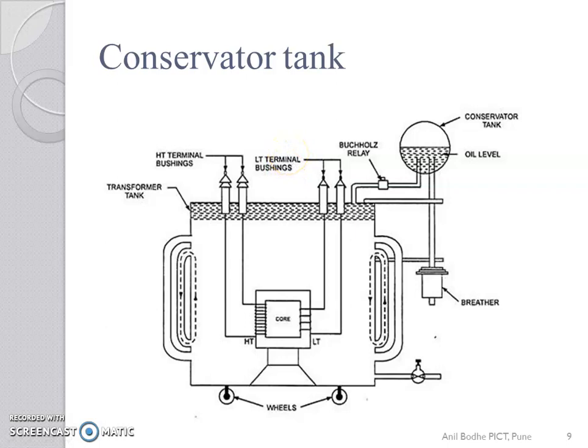Let's elaborate on it. Transformer secondary current depends on load. Transformer secondary current depends on load, and the transformer load is never constant. Because of this varying load, the transformer secondary current is also changed, and hence the power dissipation in the form of heat occurs, and accordingly temperature change occurs in the transformer.